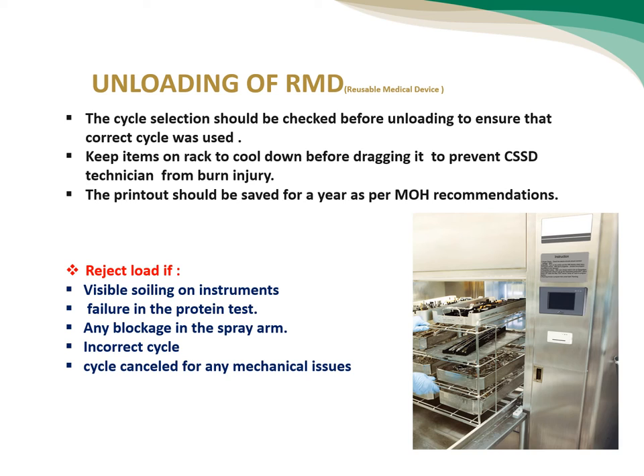Unloading the washer disinfector, or unloading the reusable medical devices from the washer disinfector: we have to check the cycle, whether it's the correct cycle or not. Keep the items on the rack before you drag them out from the washer disinfector, to prevent any burn injury to the technician. Of course, we have to save the printout in a logbook for 1 year, as the MOH recommended.